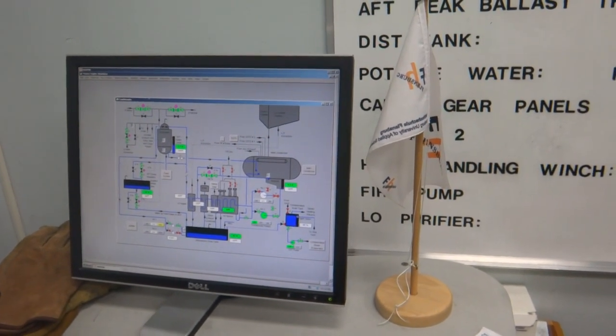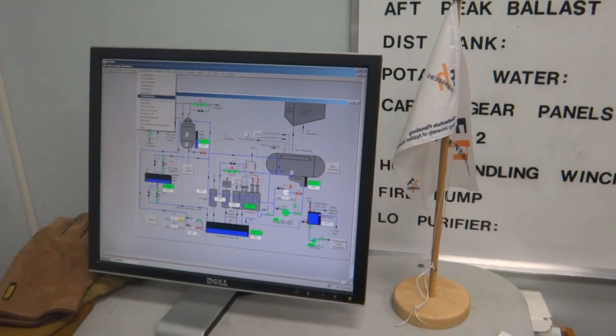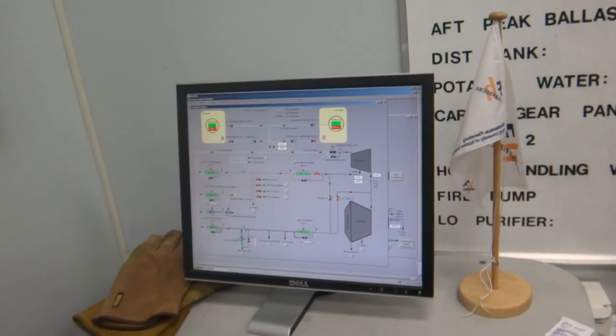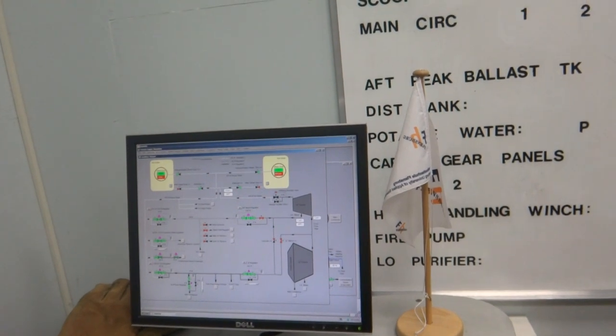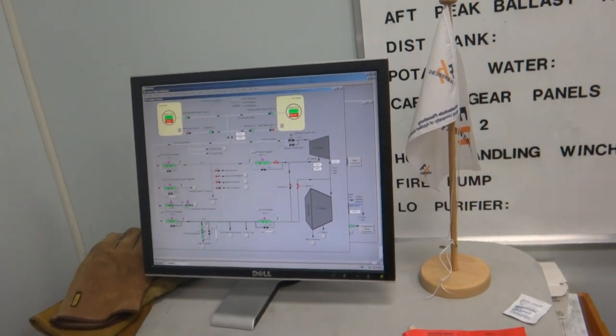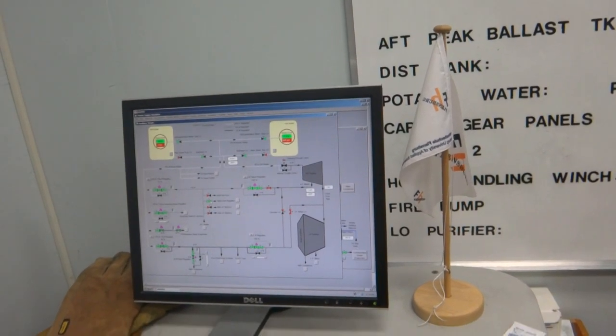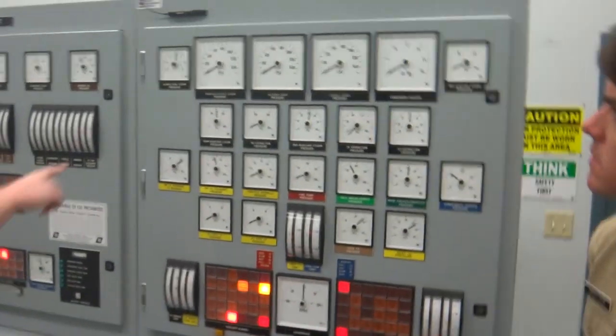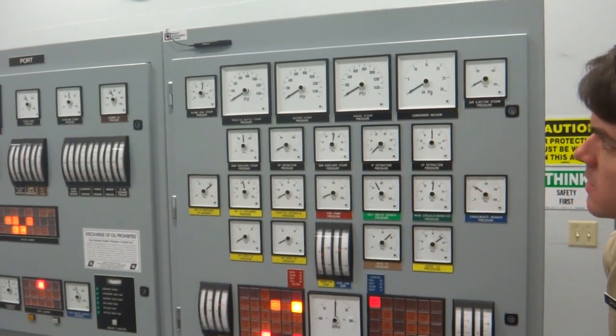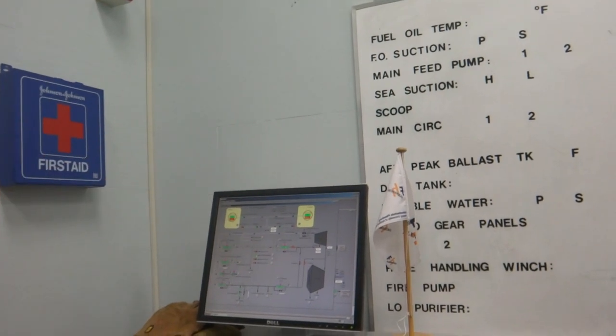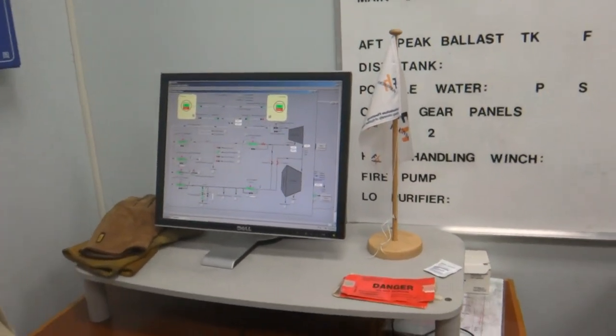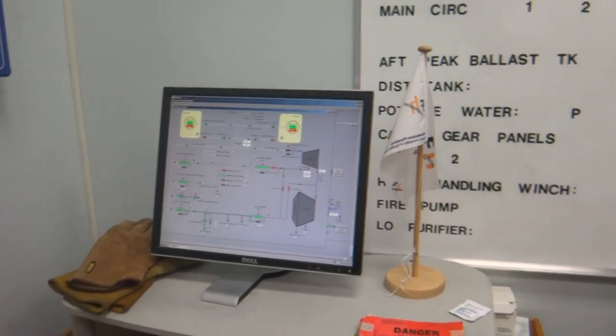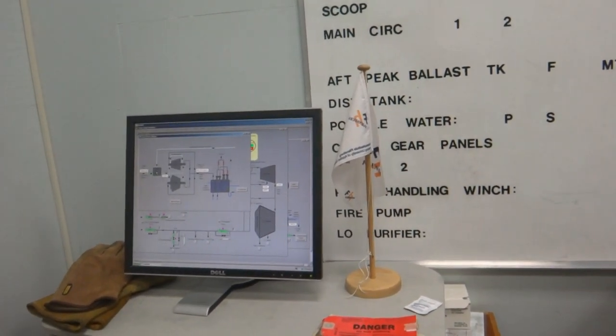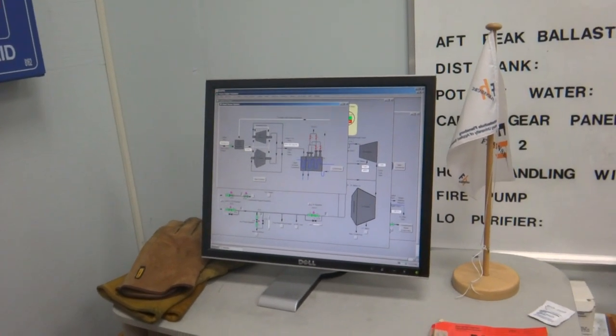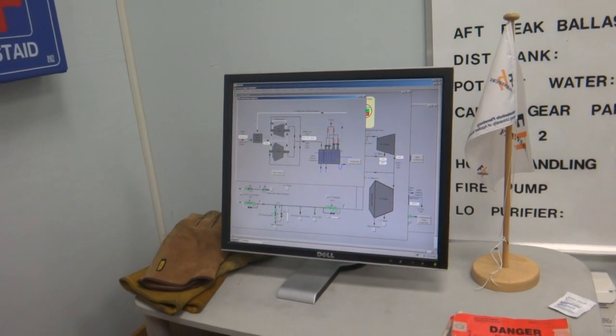I'm going to close that. We'll go to auxiliary systems. We'll go to auxiliary steam. And now we got the 150 pound on. If I click on this, look at your gauge on the upper left there, you'll see you have 3 psi on the gland seal steam. And that's just making a cloud there on the gland on either side of the turbine to exclude the air. It's positive 3 psi. That's 150 pound steam going in? Yeah, it goes through a regulator though. It goes through this regulator right here. So it's 150 going into the regulator and it's 1 psi or 2 psi coming out.